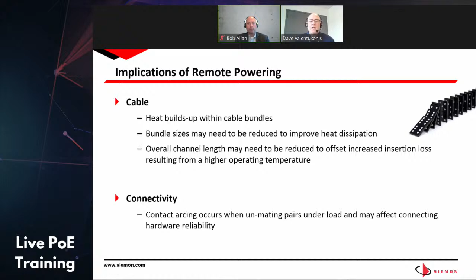So when you talk about temperature rise of the cable, because you are introducing power in addition to the communication, you're typically going to get a heat rise. When talking about the characteristics of structured cabling, the insertion loss is evaluated at about 20 degrees C, or 68 degrees Fahrenheit. A lot of your environments are going to be warmer than that, and there's going to be additional heat buildup in your cable. So the impact has to be managed: how much heat buildup you allow for, and what you can do to offset the implications, especially from an insertion loss perspective, which is what we're most concerned with.